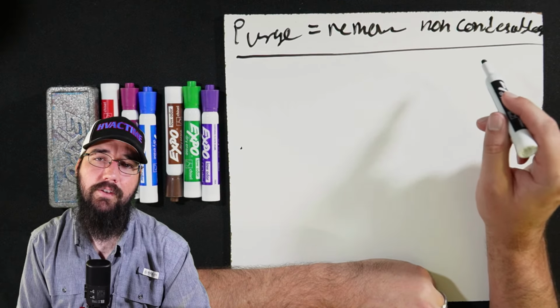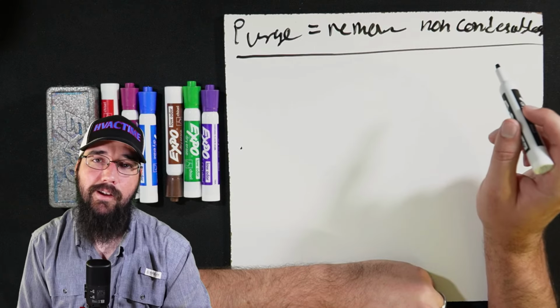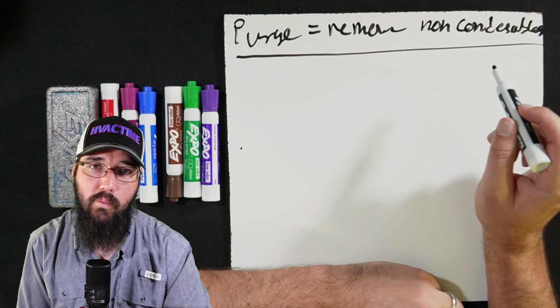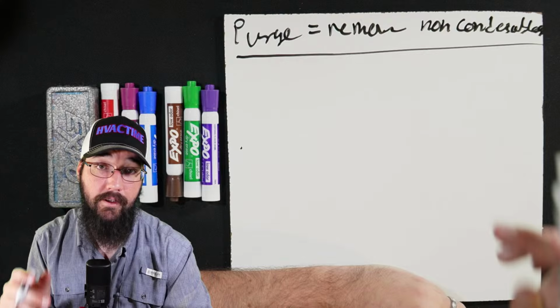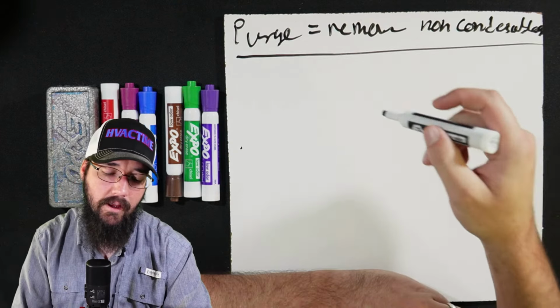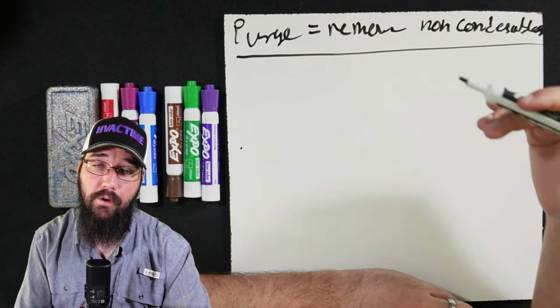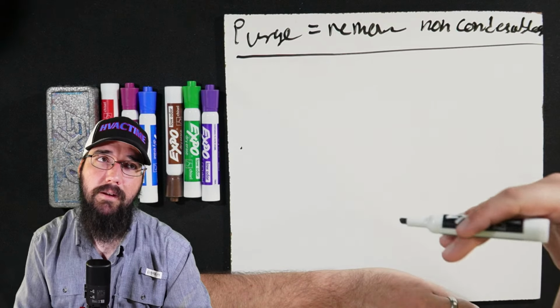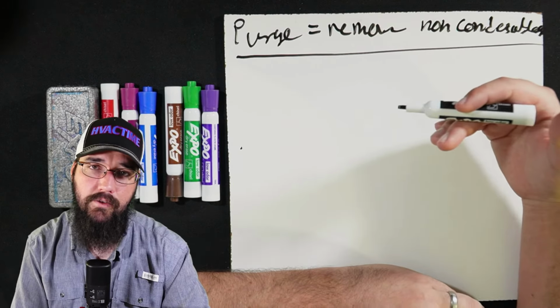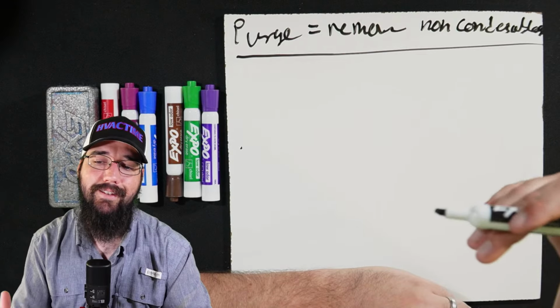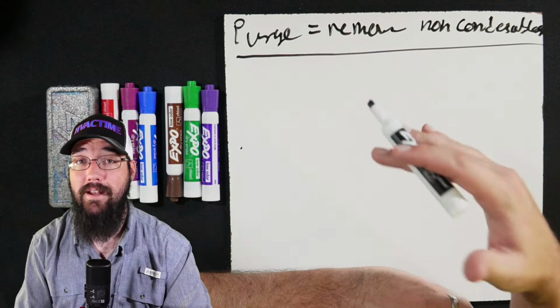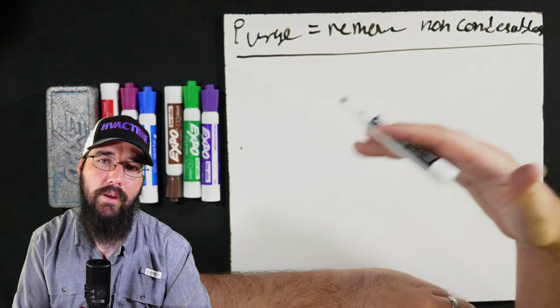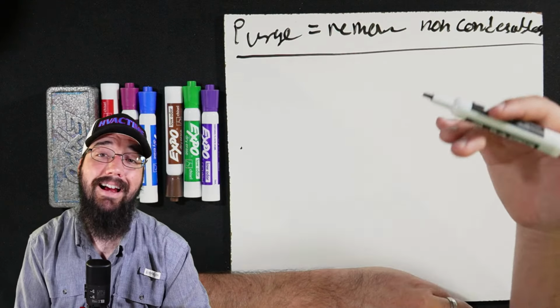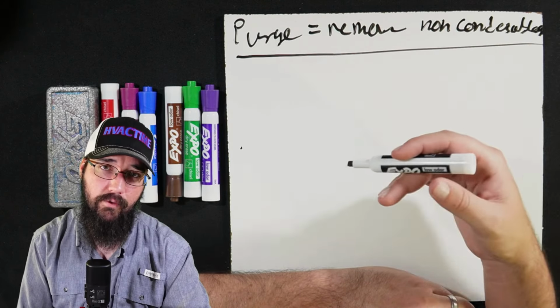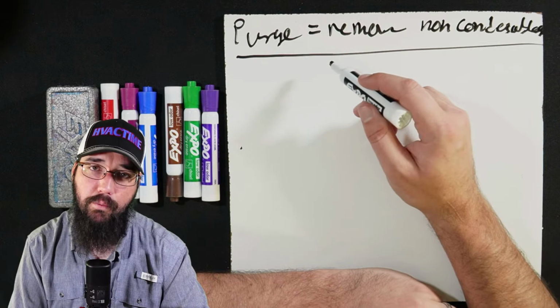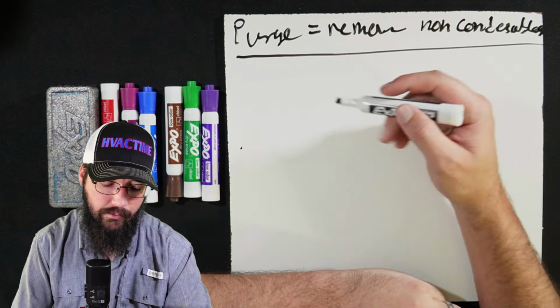We are processing non-condensables, which does not include the water or the moisture that gets drawn into the machine if there is a leak. But that is the whole purpose of a purge, is to process those non-condensables out so that the machine can still function when leaks happen. Not if leaks happen, but when they happen, the same way they would on a high pressure machine, which would be your 134A. Examples of low pressure would be your R11 or 123.